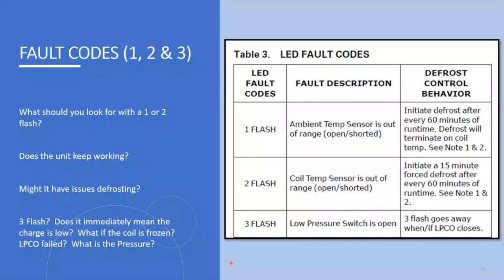Going through the error codes on the defrost board, and these are the red LED next to the green one. 1 flash means ambient temp sensor is out of range. So it doesn't mean that it's out of calibration. It means that it's a direct short or completely open. In that case, it's going to initiate a defrost every 60 minutes of runtime. And defrost will terminate on coil temp, because we still have the coil temp sensor, we just don't have the ambient to reference it against.